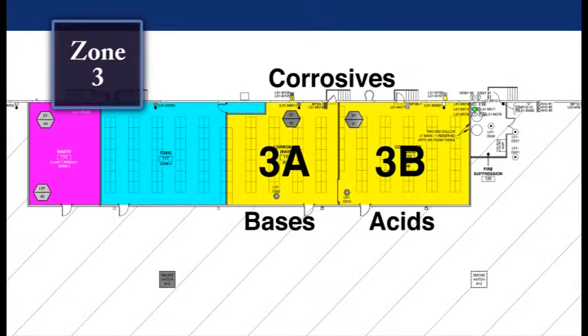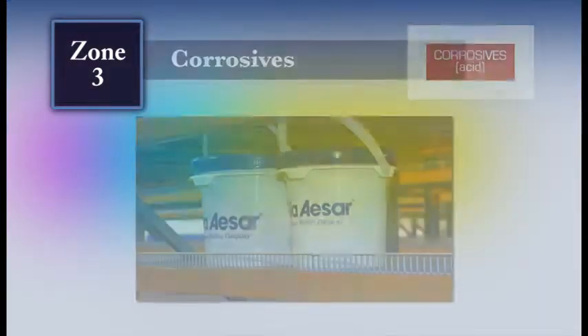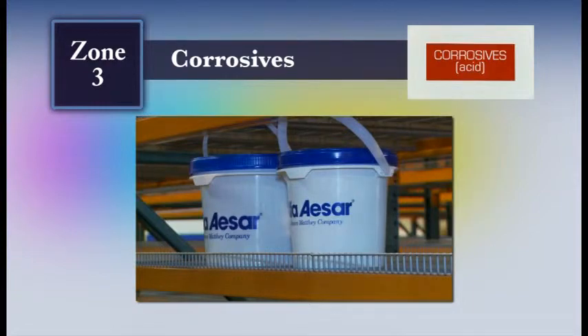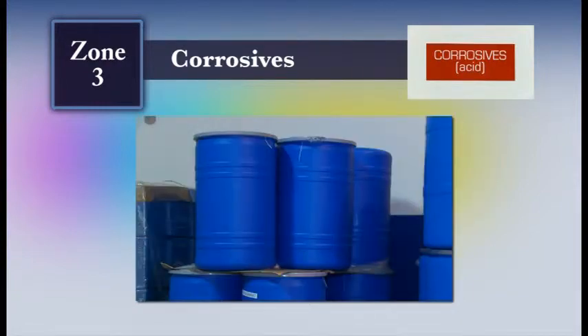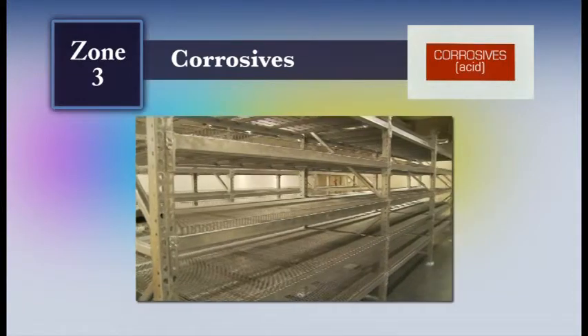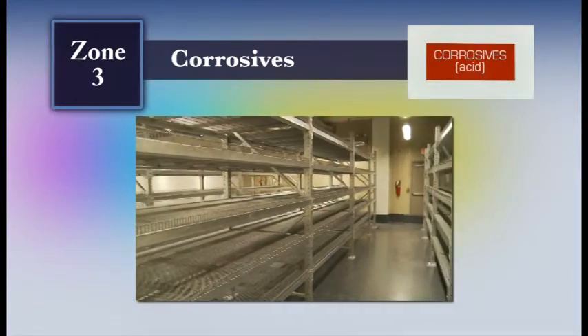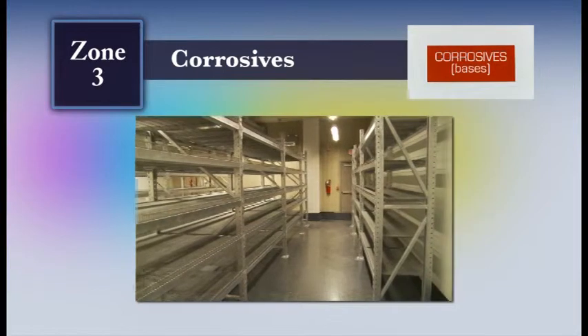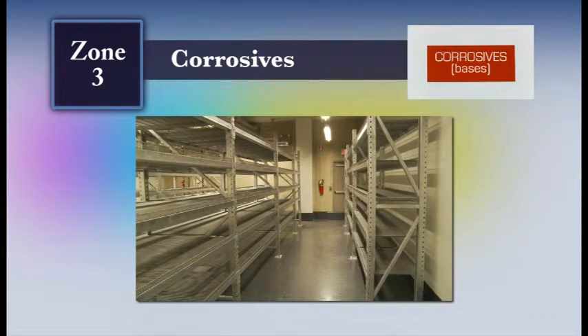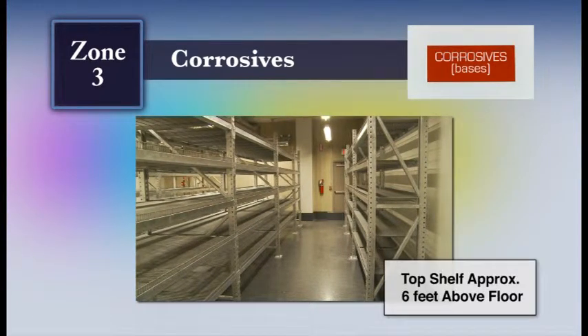Product in these areas is primarily stored in plastic pails, drums, and containers that vary in size from 1 to 2 gallon containers up to 55-gallon drums. The racks are installed to create a space between each rack and any adjacent wall. Rack height varies but is generally 3 or 4 levels high. The elevation of the top level is approximately 6 feet above the finished floor.